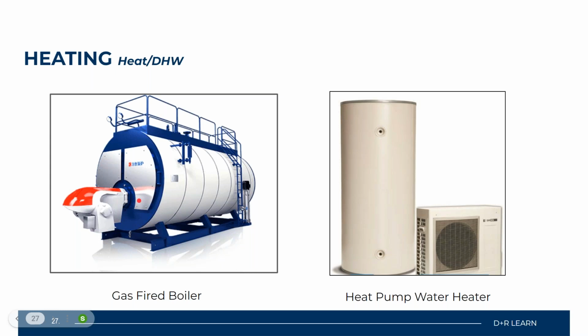And this boiler uses gas or any type of bulk LPG that's stored directly on site in some sort of a storage tank. The gas that's brought into this system is burned in the boiler's combustion chamber located up here and warms any type of water that's inside of it to around 158 degrees and higher. Okay, you have oil-fired boilers that pretty much look the same way, and also electric boilers. I haven't personally seen them in this round configuration, but you do also have electric boilers as well.